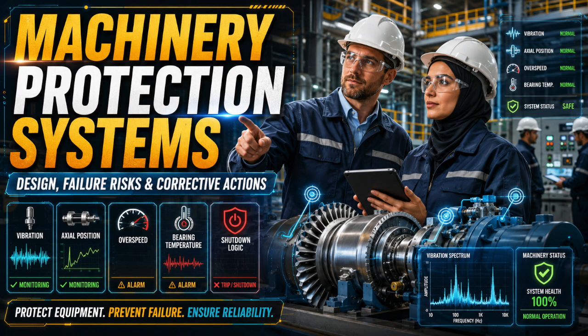Does 2 out of 3 voting work as expected? Will a single failure alarm but not trip? Will 2 failures trip where required? Have relays and final elements been tested? Overspeed protection is not a place for assumptions.